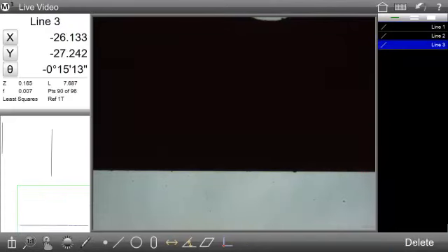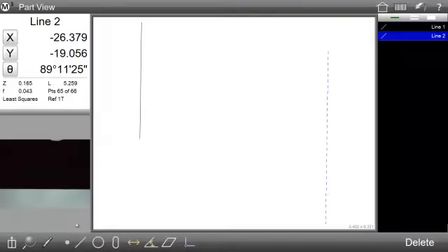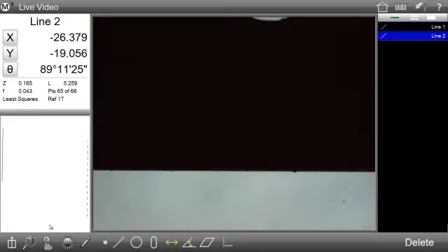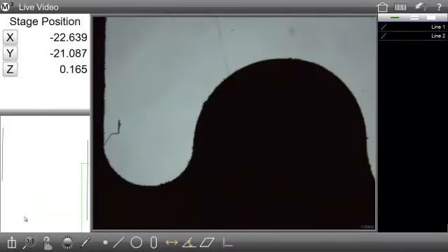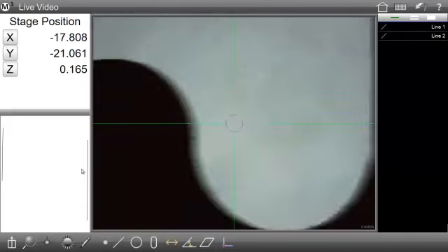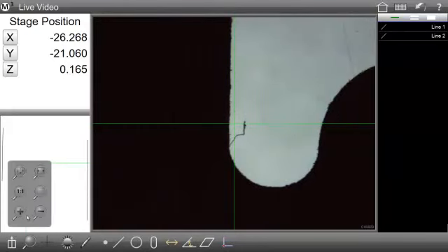The next button in the bottom toolbar is the Part View and Live Video Zoom menu. This menu is context sensitive to the part view or live video view, depending on which you're looking at, and contains the various zoom function buttons available in the M3. Next to the Zoom menu, we have the Probe menu. Select any video probe button type to assign it to the active video probe. Simple and active crosshair, measure logic, and the autofocus tool can all be chosen from this probe menu.